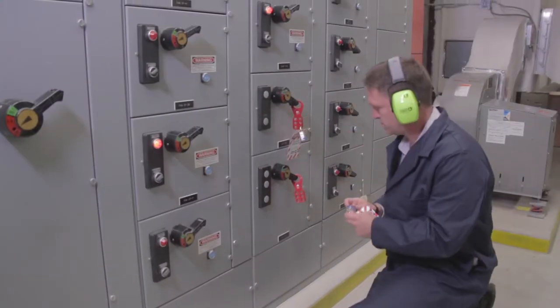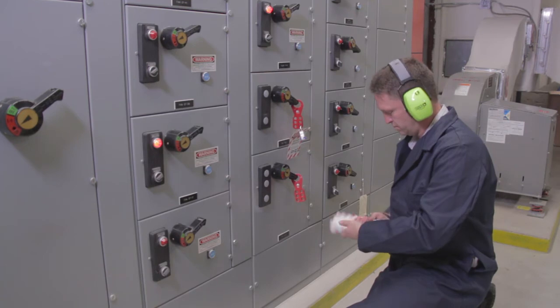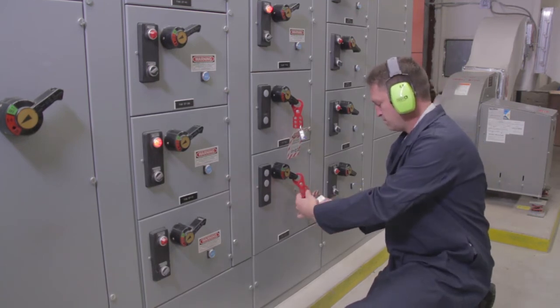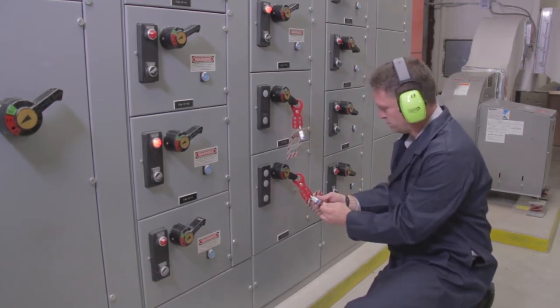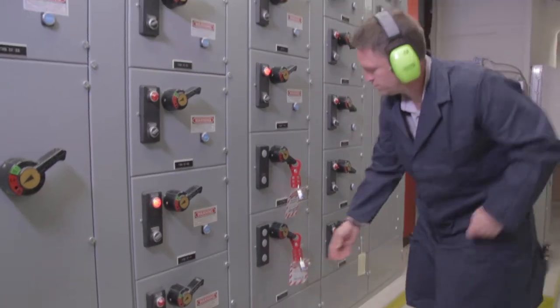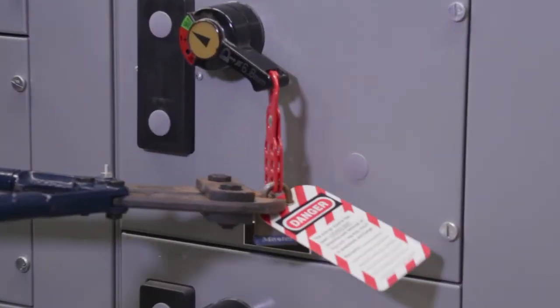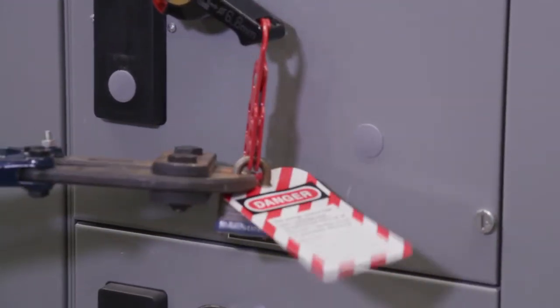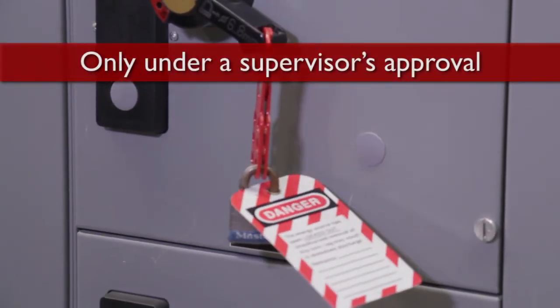If you put the lock on, you are the only one who can remove or authorize its removal, except in very special circumstances when there are multiple lockout devices and workers involved. If you're not available to remove your lock, board procedure will allow the lock to be cut off, but only if a supervisor has deemed it safe.